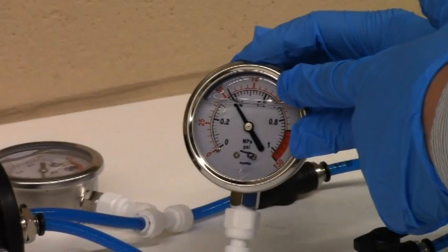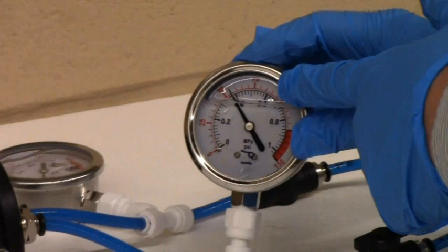Make sure to achieve the filter inlet pressure of 50 psi or above by closing the bypass valves only. Turn on the two inline TDS meters. Make sure the filtrate TDS meter 1 shows below 20 ppm and the reject TDS meter 2 shows below 100 ppm. If not, keep adding tap water to the bucket and keep flushing the pump and filter.